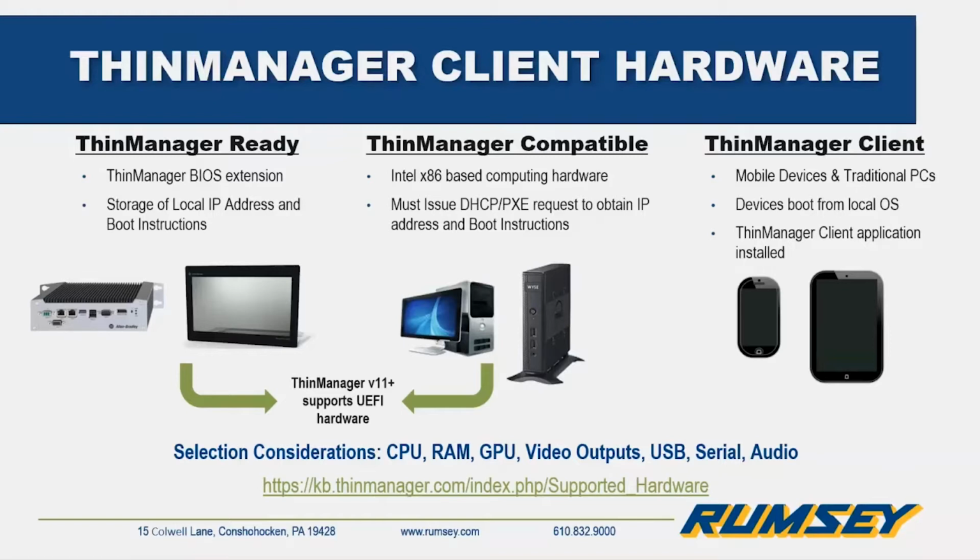They may not know what ThinManager is, but these clients can use the pre-boot execution environment, or what they call the PXE boot, to obtain the firmware and the configuration from ThinManager, and they can be managed exactly the same as a ThinManager ready client once that is set up initially. So out of the box, you do have some configuration with a non-ThinManager ready client where you have to set up that PXE, that pre-boot execution environment. Once you've done that, you can then boot that directly like any other ThinManager ready client, and ThinManager takes over from there.